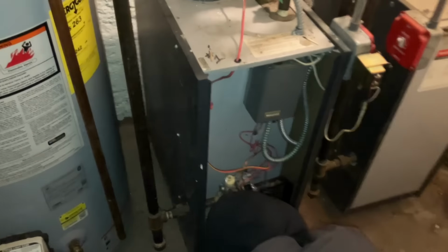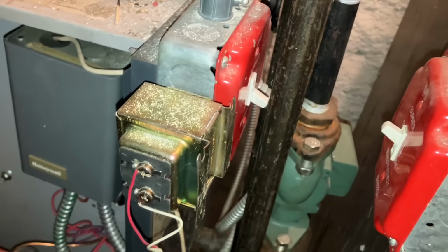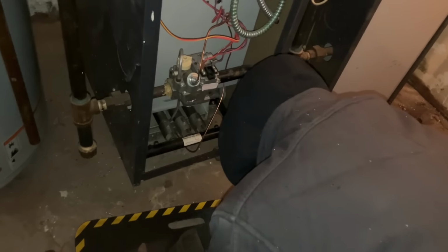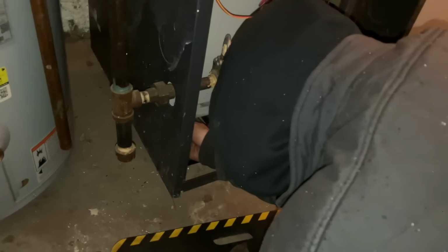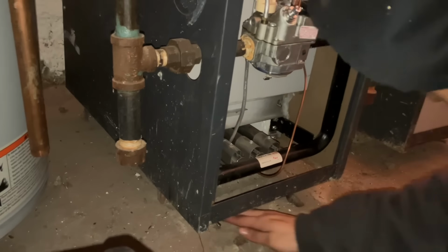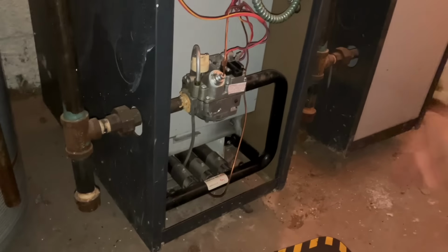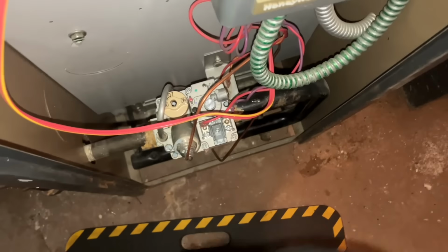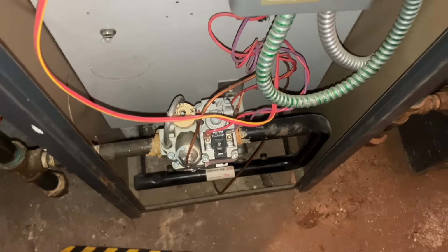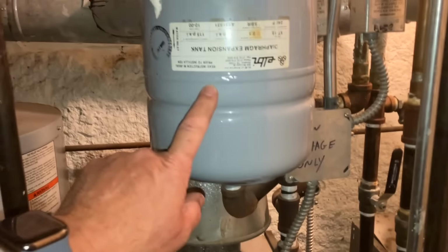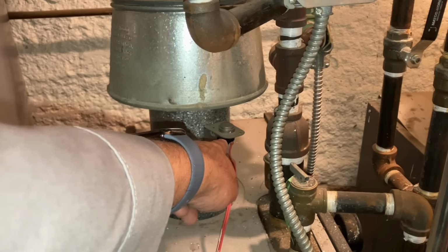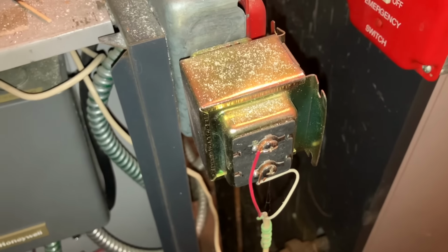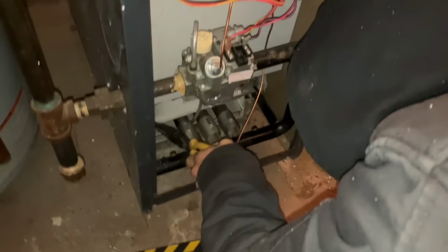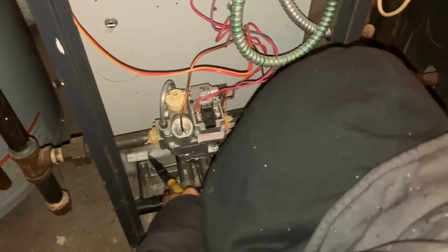Okay. All right, we're going to start maintenance on this Weil-McLain. We have the power off. Derek's removing the wing nuts that expose the combustion chamber. And then he's going to pull out the burners, and we're going to vacuum out the combustion chamber, clean the burners. Well, it looks like a nice brand new gas valve there with a thermocouple. Looks like someone took some pride there. Very nice. There's our aquastat relay, expansion tank, 2 zone valves, blocked vent switch, automatic vent damper, transformer for those zone valves. There's the circulator. That's the standing pilot gas valve. And down there, is there a rollout switch? No, there is not a rollout switch.